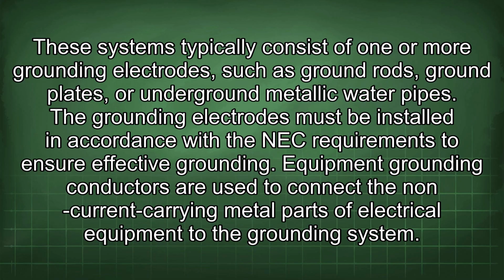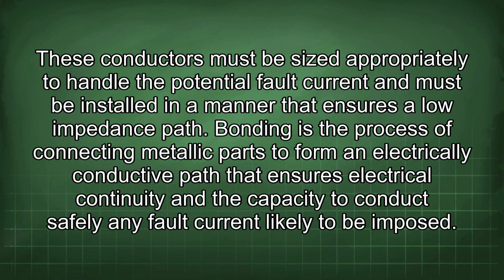Equipment grounding conductors are used to connect the non-current carrying metal parts of electrical equipment to the grounding system. These conductors must be sized appropriately to handle the potential fault current and must be installed in a manner that ensures a low impedance path.